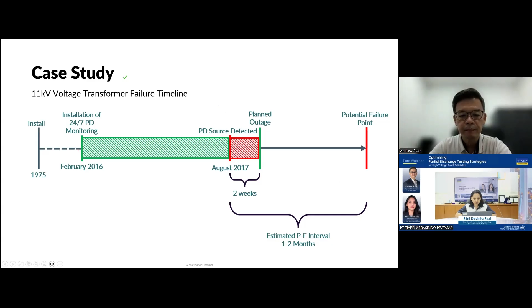So 2 weeks later, they planned an outage. They shut down and racked out the circuit breaker. They were able to see a crack in the insulation and a burn mark in the circuit breaker body. Basically, if they had waited another 1 to 2 months, there maybe would have been a flashover. But they were lucky, and they planned all this with the real data and the guidance provided by the monitoring system, so they were able to prevent these outages. So that is another case study.